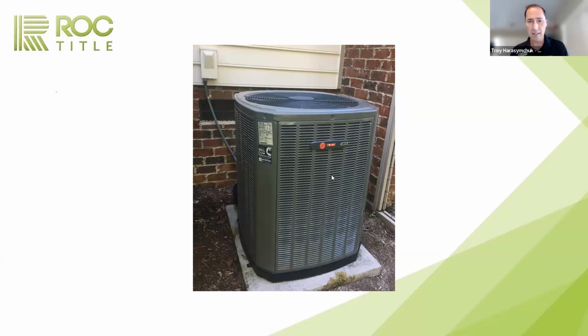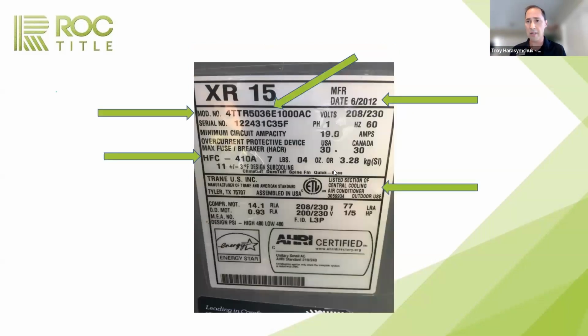But this is a Trane. This is my old system, and I just want to show you how easy their labels are. American Standard's the same way. So you can see how old the system is. I don't even have to use the app because it shows right on there. It's from 2012. Is it a heat pump or air conditioner? I don't have to look that up. It says right there, air conditioner.